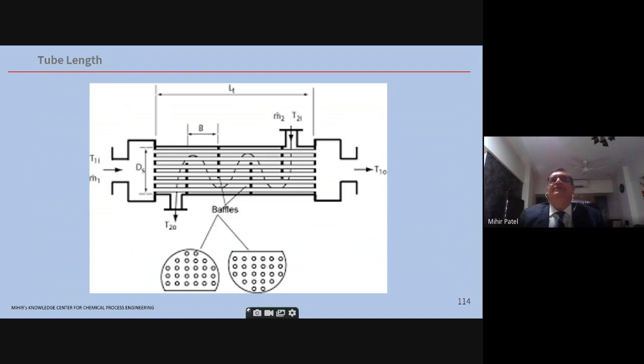So tube length basically affects cost of heat exchanger. Longer tube length means smaller diameter of exchanger and fewer tubes. Typically, tubes are 8, 12, 15, 20 feet in length. Okay. For mechanical cleaning, maximum 20 feet tube length. Maximum possible is still 40 feet. But you have to be careful because transportation and all you have to also look at. Thumb rule is shell diameter to tube length is 1/5 to 1/15. Okay, this is a thumb rule basically. Maximum transportation length is 30 meters.